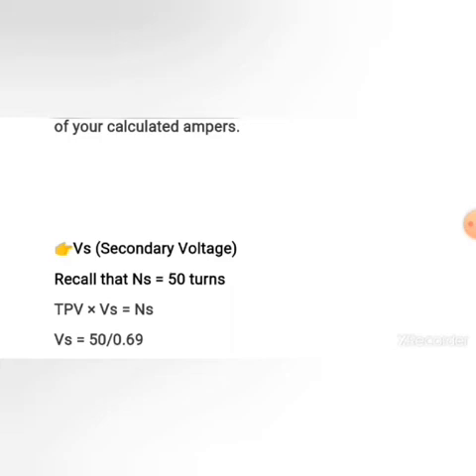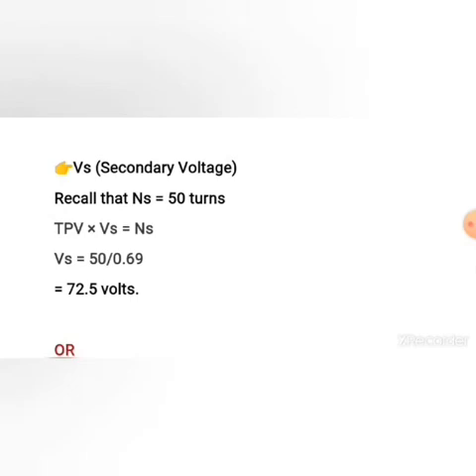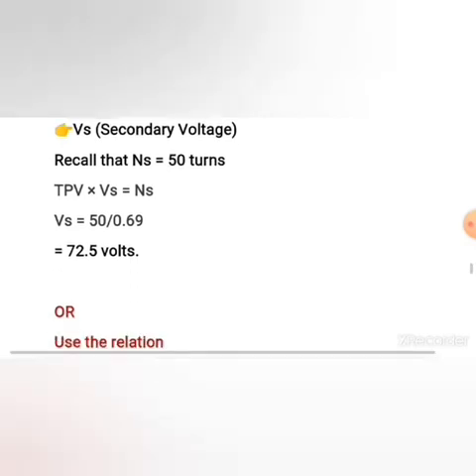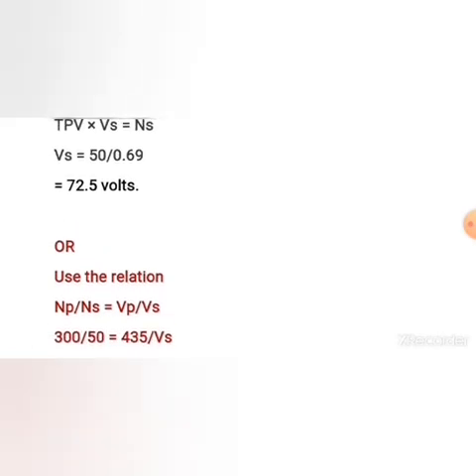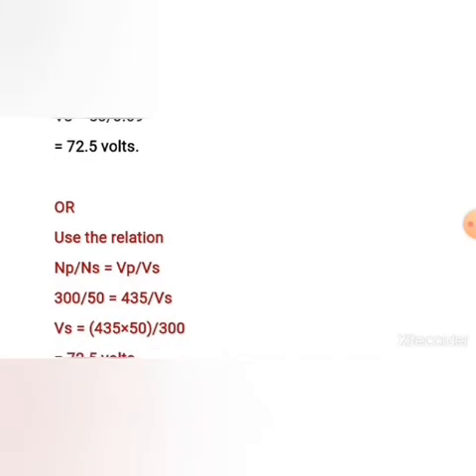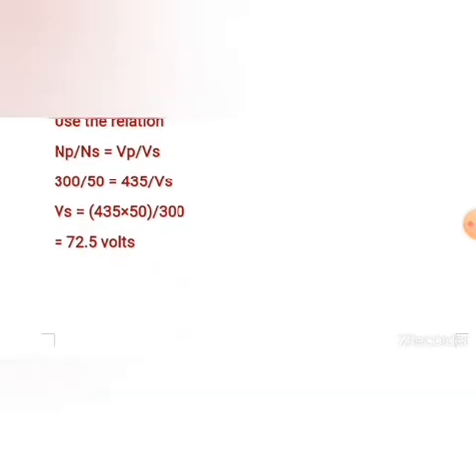For secondary voltage, using the same formula — turns per volt times secondary voltage equals number of turns — we substitute and make secondary voltage the subject: 50 turns divided by 0.69 turns per volt gives us 72.5 volts. You can also use the popular transformer ratio formula: Np over Ns equals Vp over Vs. Substituting 300 turns primary, 50 turns secondary, and 435 volts primary, we still get 72.5 volts as our secondary voltage.